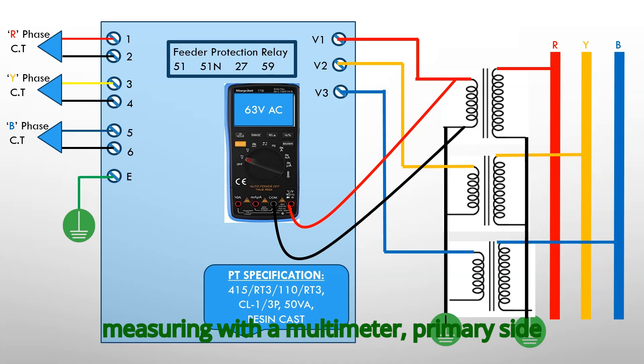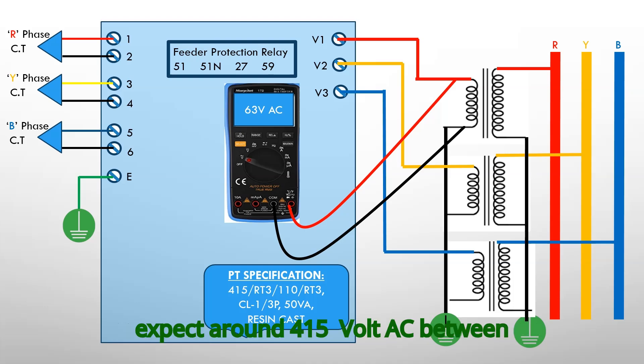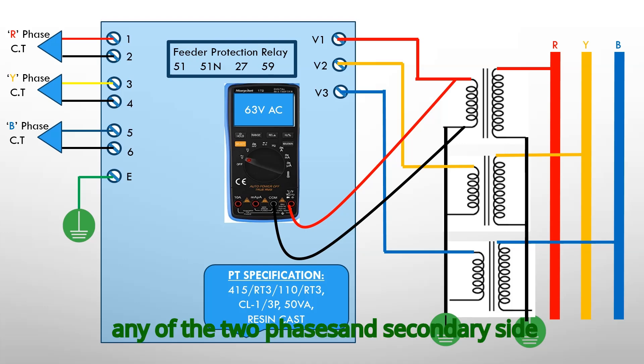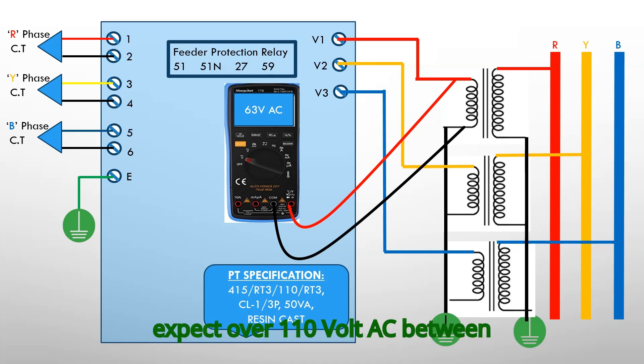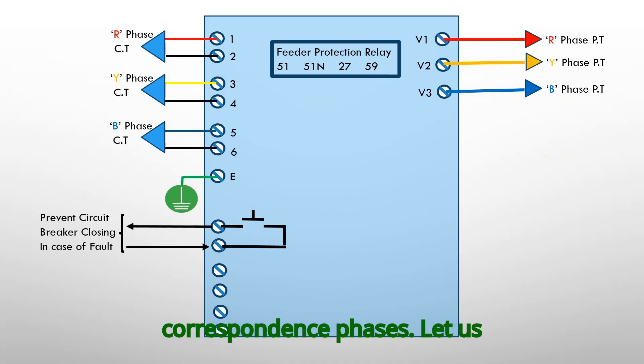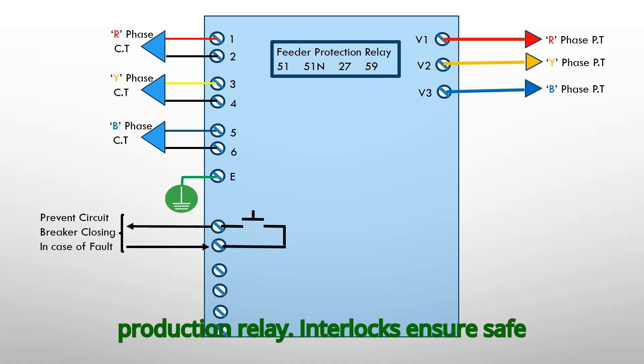When measuring with a multimeter, on the primary side expect around 415V AC between R-Y, Y-B and B-R phases. On the secondary side expect around 110V AC between the corresponding phases. Let us explore the interlocks within the feeder protection relay.